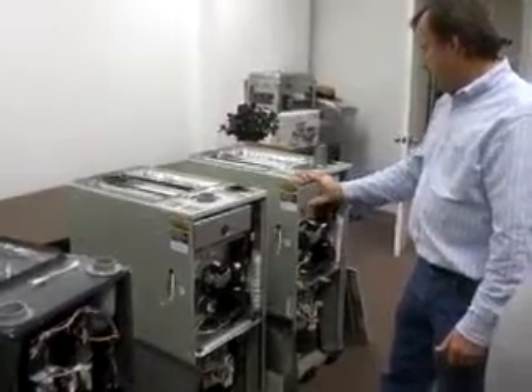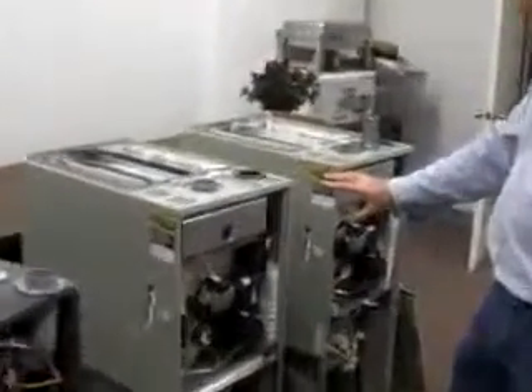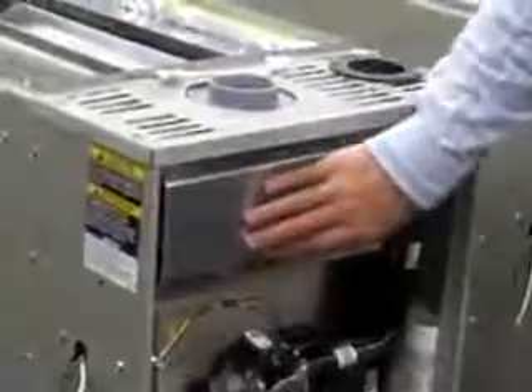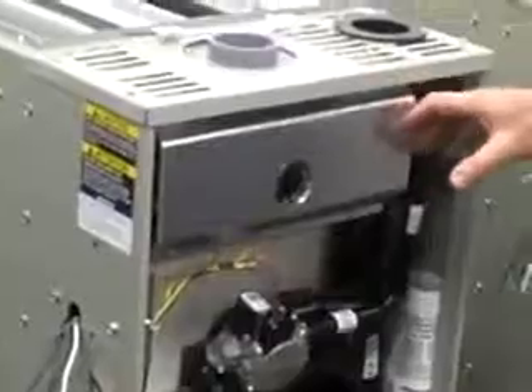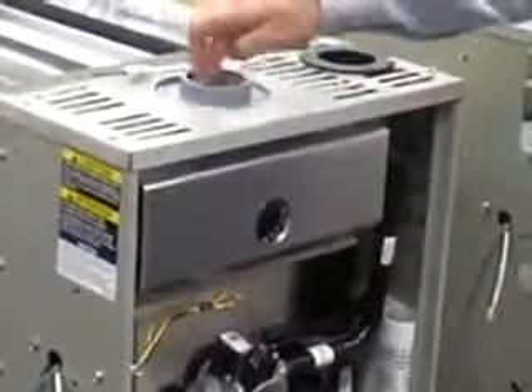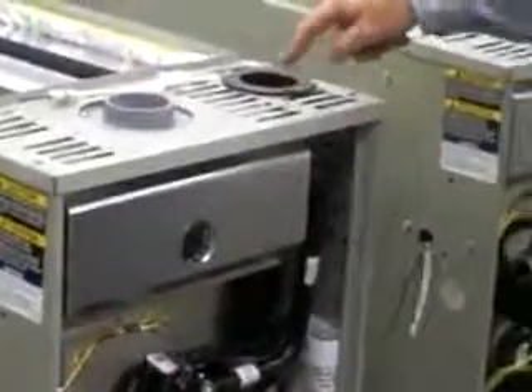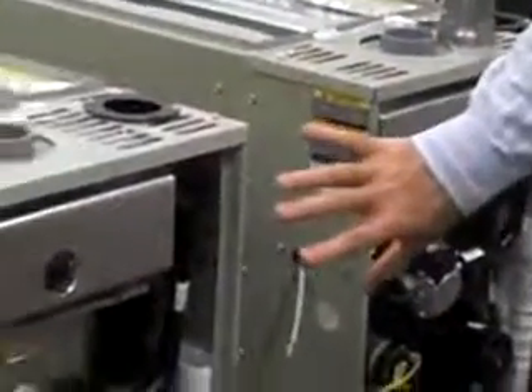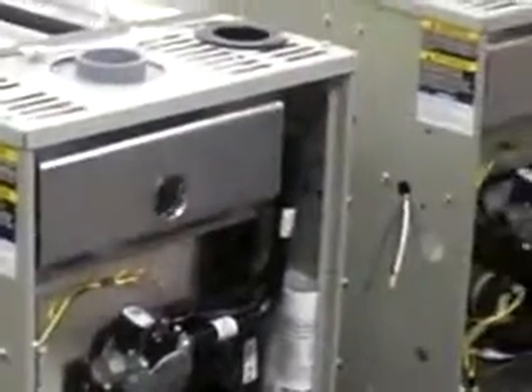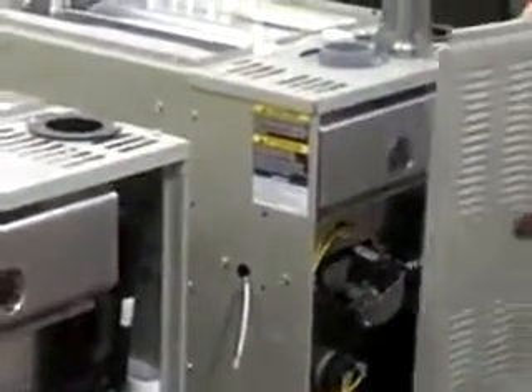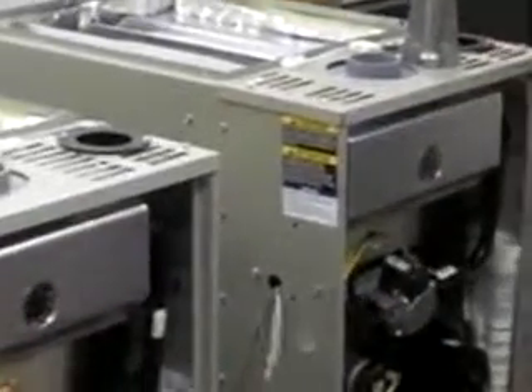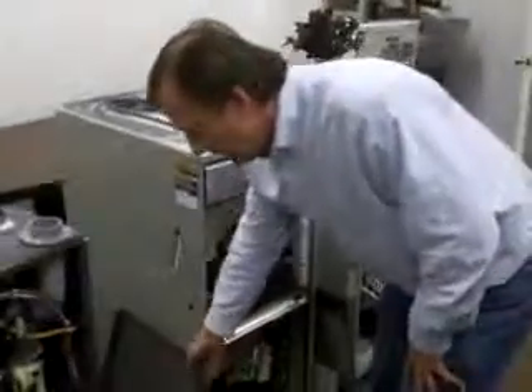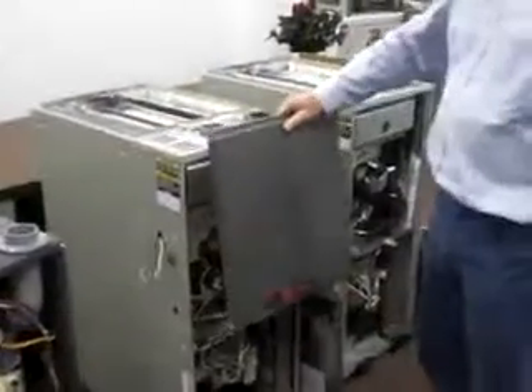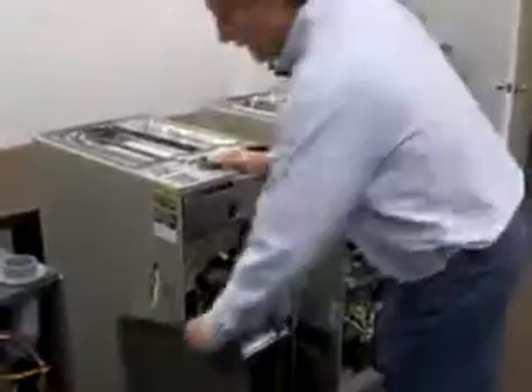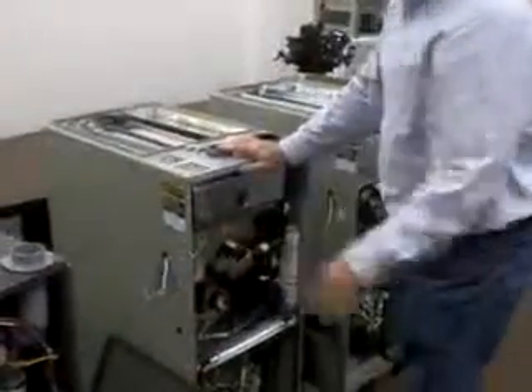When we look at how our burner boxes are designed, all the Trane 90 Plus models use an isolated combustion by virtue of a burner box, okay? We have a true sealed combustion chamber where we have outside air with an intake screen and exhaust air from the inducer. Our door can be used to protect the consumers from exposed parts, but in the upgrade model, the door actually becomes a solid door, and it will further minimize noise from the inducer, okay? So the upgrade model has a solid door.